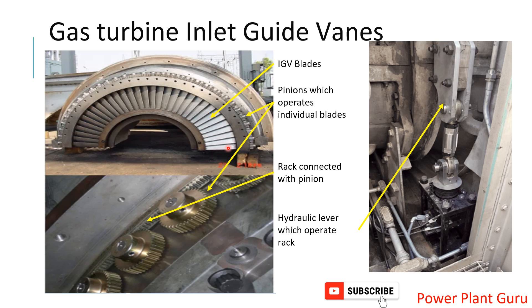It depends on the machine. For example, GE machines operate from 34 to 84 or maybe 86 degrees. But for Mitsubishi MHI gas turbines, 45 degrees is the full-close condition and minus 5 degrees is the full-open condition. We should not be confused by this — the values may change from OEM to OEM.